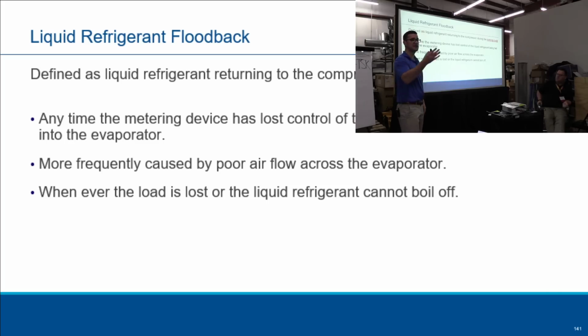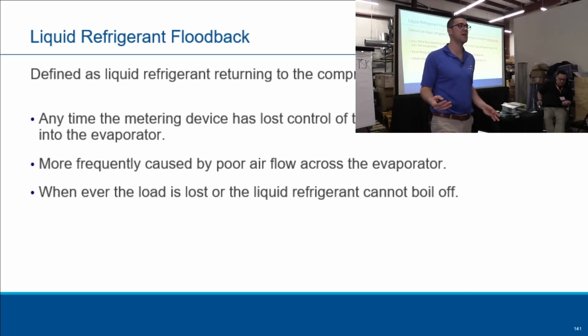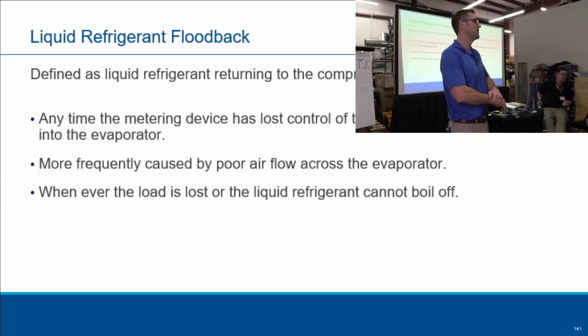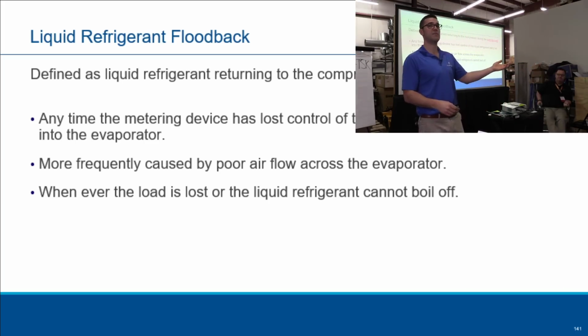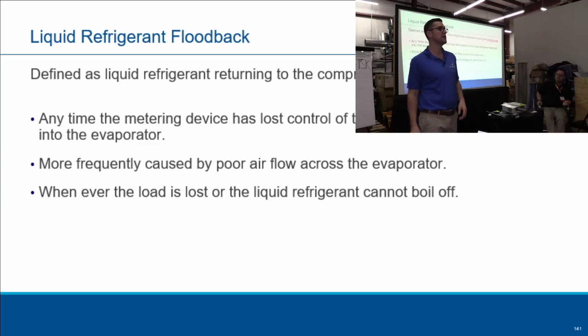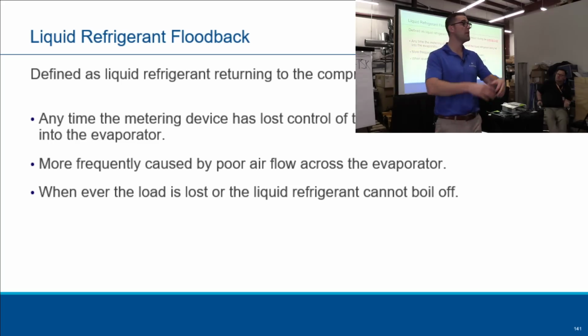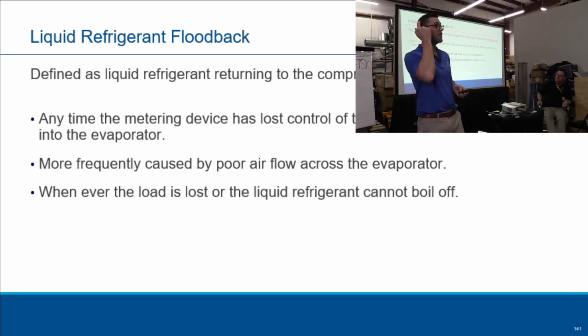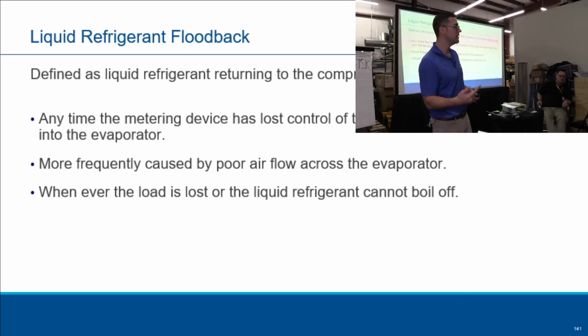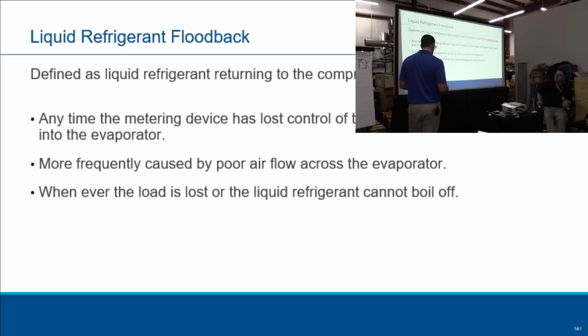What causes it? What causes flood back? Some of the things: dirt on TXVs, TXVs oversized or not sized properly, failed air conditioning, low airflow, a frozen coil, so many different things. So as the mechanic, you have to think: I've had this failed compressor on flood back, and one of these things caused it. That's very important, you need to understand that stuff, because if you can't boil off that liquid refrigerant in the evaporator, it's going to return back to the compressor.